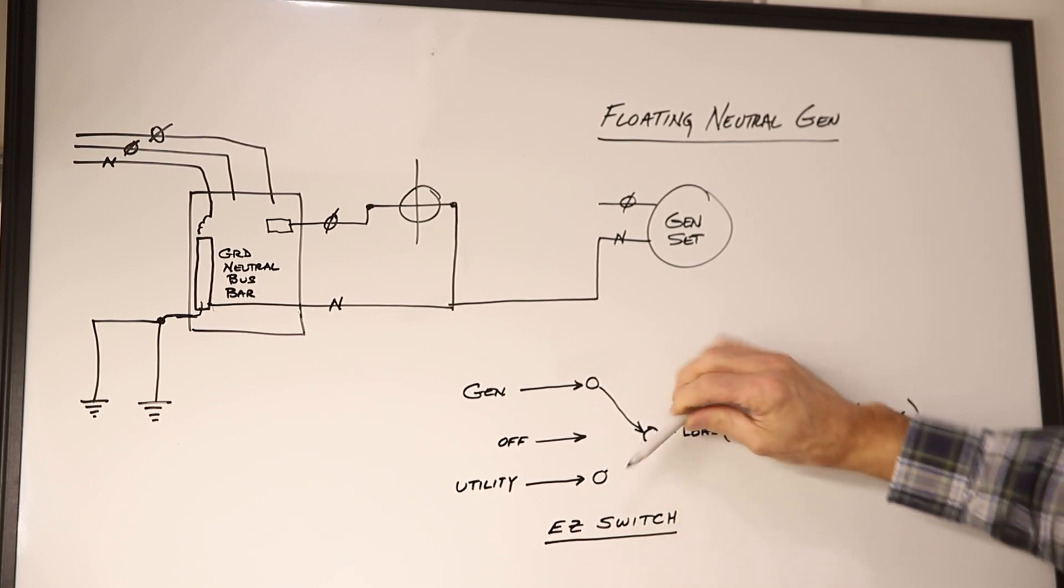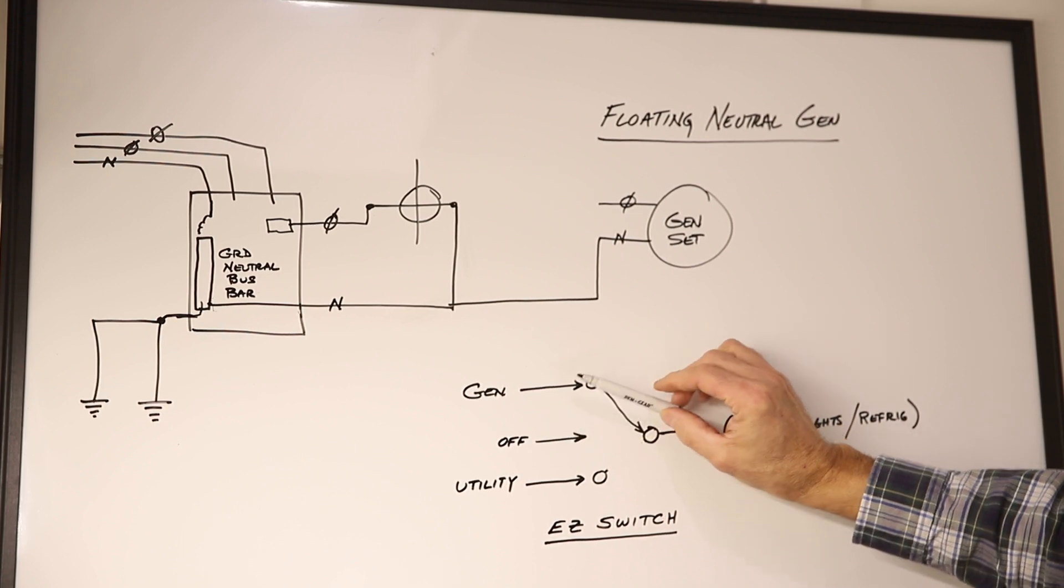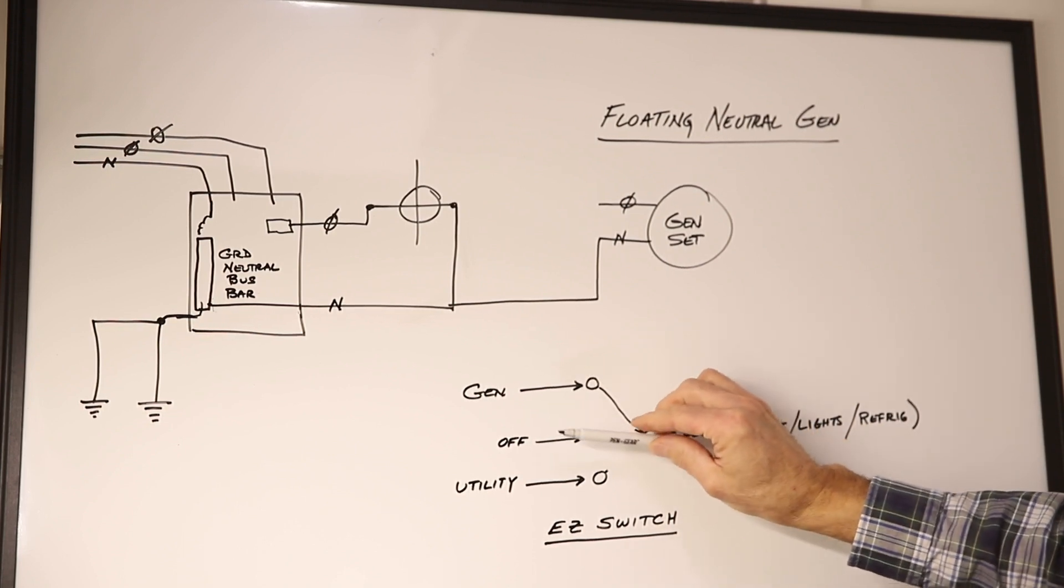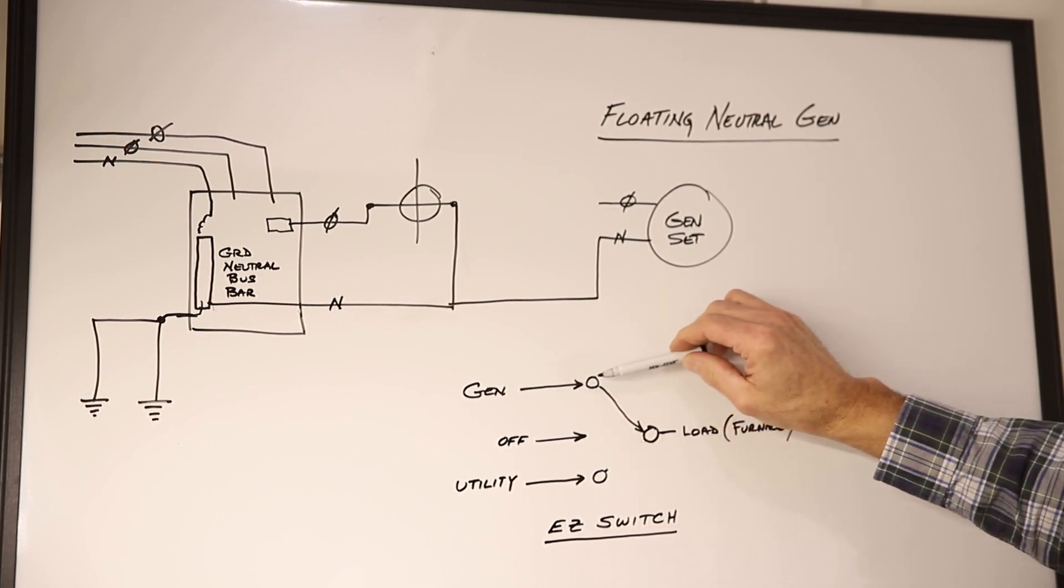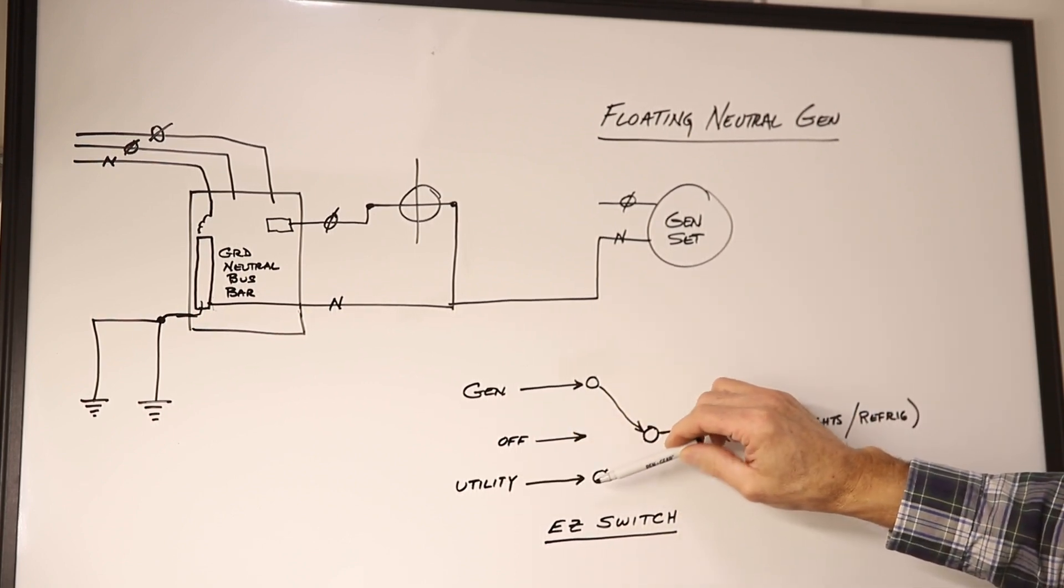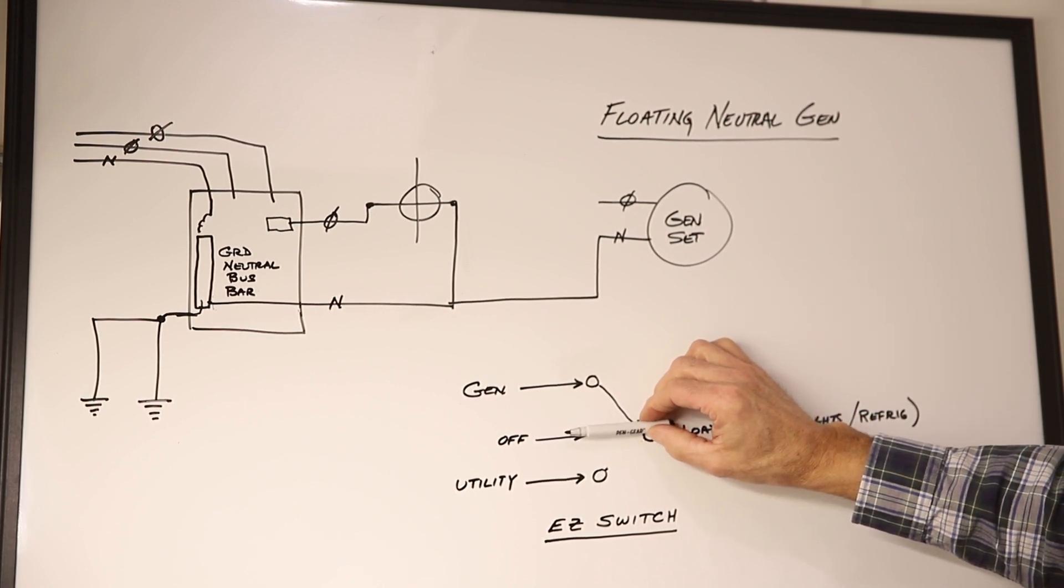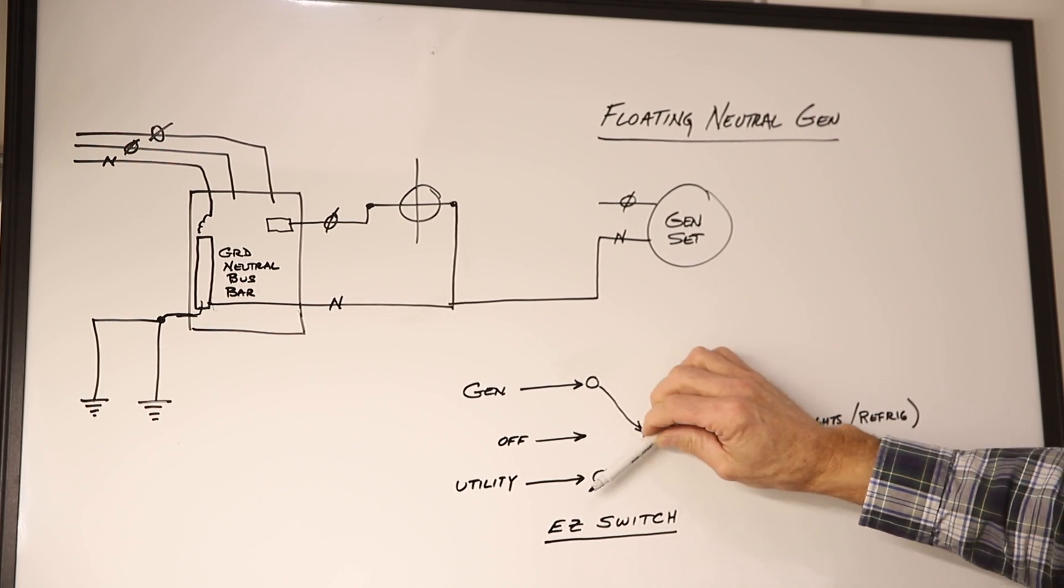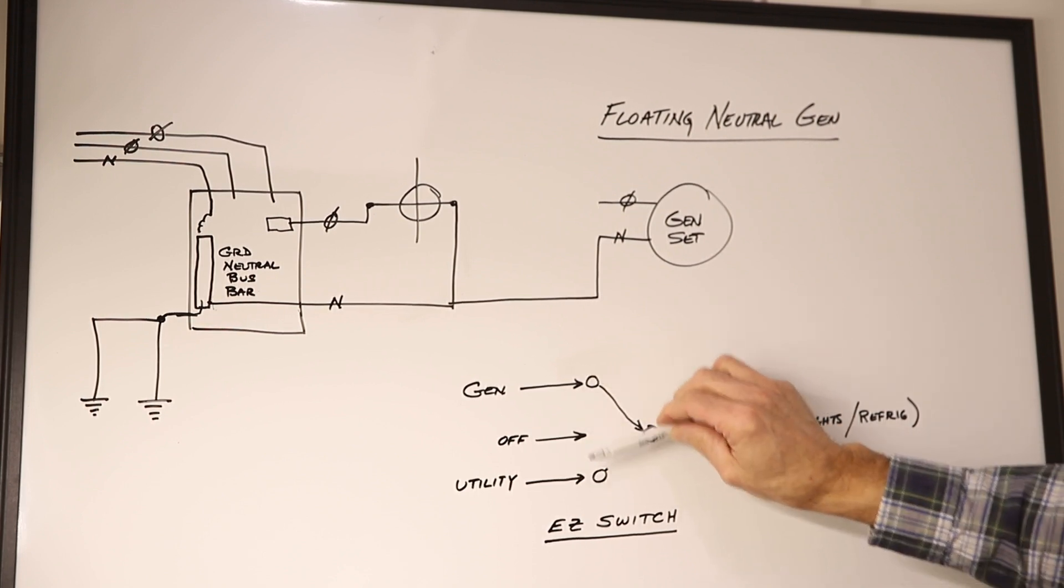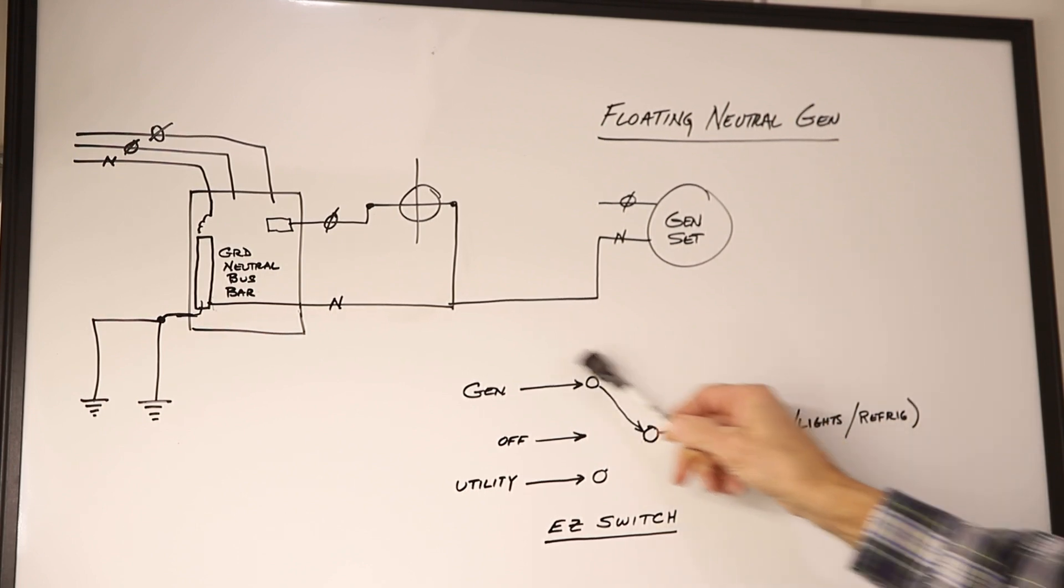You can't be in both places. It's either in utility, off or generator and the off position is there in case both have power. Your generator is producing power and utility coming in is live. This switch momentarily stops here and it's what we call break before make. It breaks the circuit before it makes the next one and stops the arc or stops a flashover.